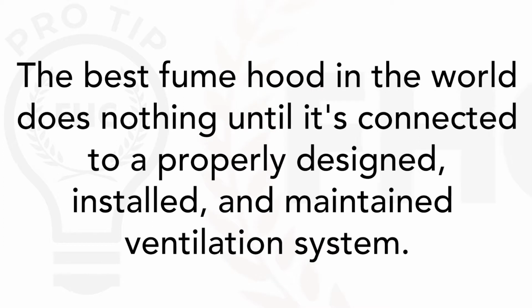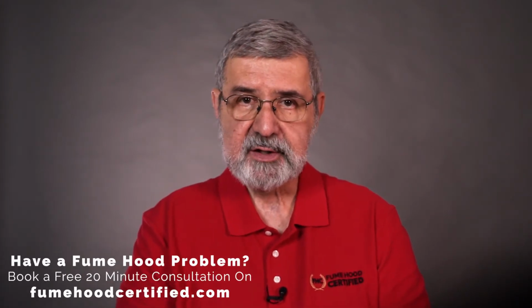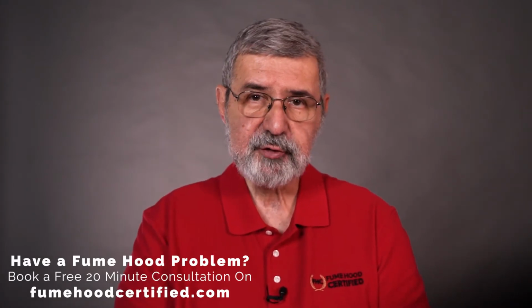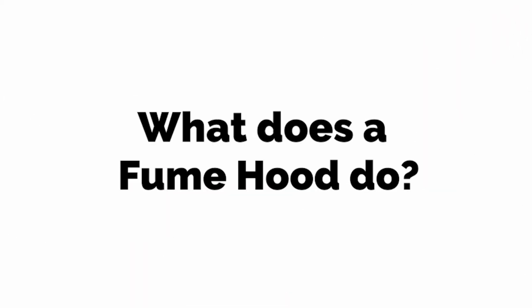Laboratory or chemical hoods are not standalone devices like a biological safety cabinet or a ductless hood. In fact, the best fume hood in the world does nothing until it's connected to a properly designed, installed, and maintained laboratory ventilation system. The fume hood is just one component in a complex mechanical system. Yet when you look at the safety warnings posted on the hood, it often says, "Make sure the hood is working." So what does working mean? To answer that question, we need to answer another question. That question is, what is it that a fume hood does?